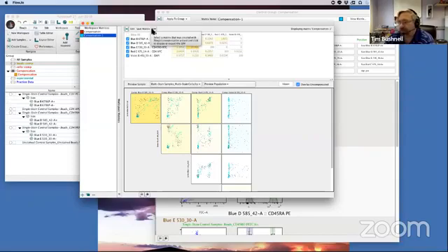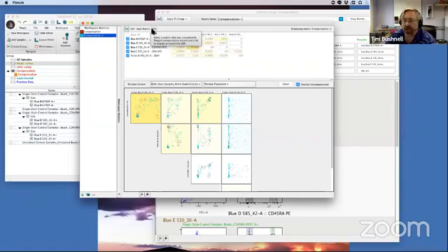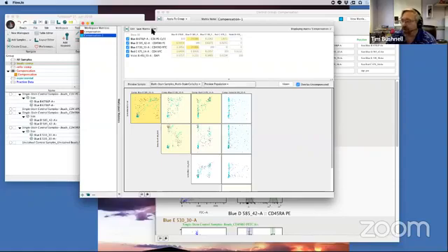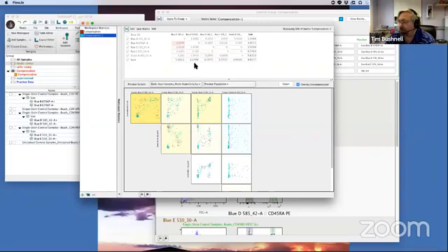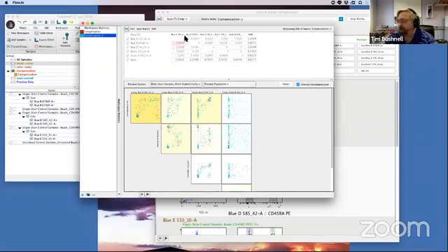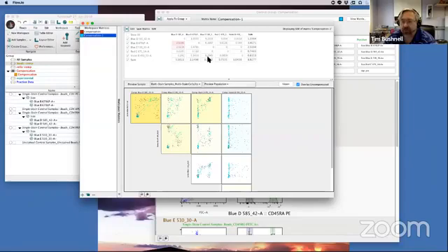The other thing we can do here is calculate the SSM or the spectral spillover matrix. And this is a very useful tool to understand the error that each of the detectors receives and the error that each fluorochrome contributes so that you can help better, one, design panels because you know what's more sensitive and what's less sensitive. And two, you can use this for tracking. So if I click on this, I'm going to hit display SSM. And you're going to see here the spectral spillover matrix. And you can see we can sum across in both directions how much, in this case, how much error given fluorochrome, given detectors receiving. And in this case, how much a given fluorochrome is contributing to the whole panel. And you can identify areas where there's significant issues. And in this case, this is only a four-color panel. So we don't have a lot of issues.